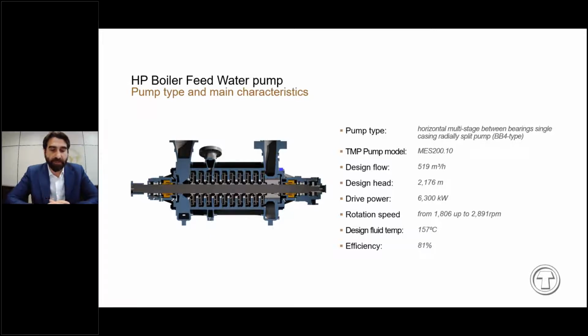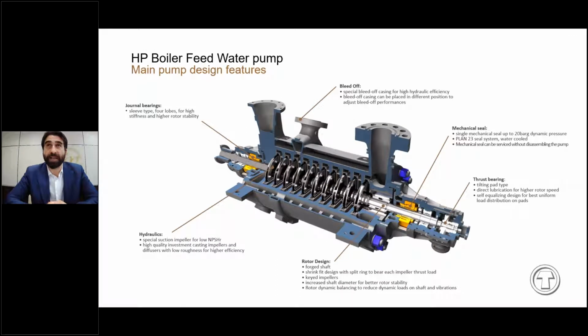However, in our portfolio, pumps of this family can reach very high efficiency, up to above 84%, depending on the size, the speed, and of course the fluid temperature as well. Okay, in this slide, we can see the section of the pump that we are going to test. You can see the 10 impellers and diffusers. They are manufactured using a high quality investment casting process, and then they are polished in order to have very low roughness and very high efficiency. The first impeller has been designed for low NPSH required, and it is different from the other stages, which are designed for high efficiency.